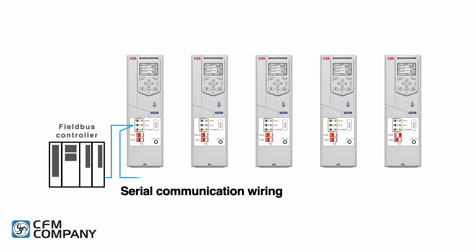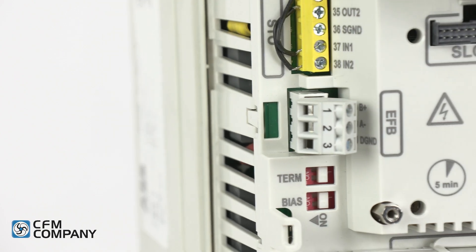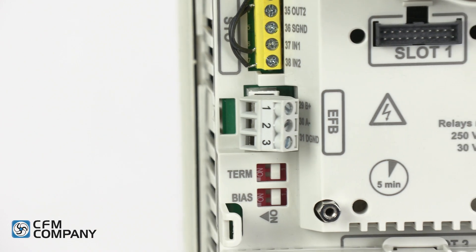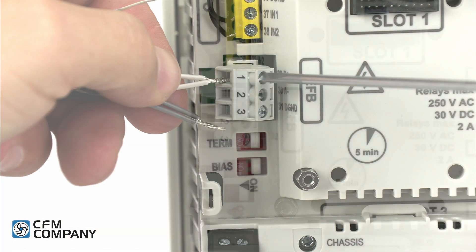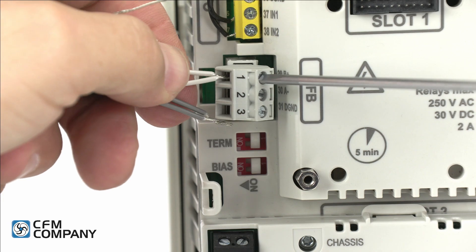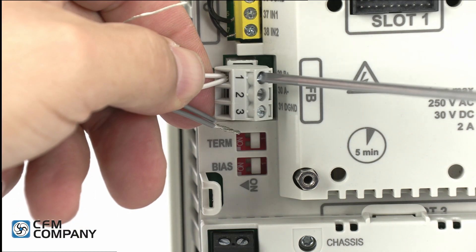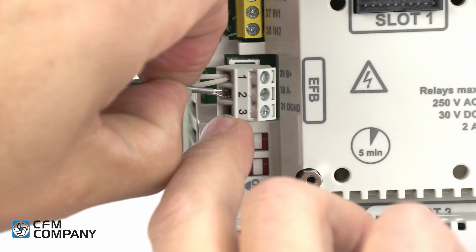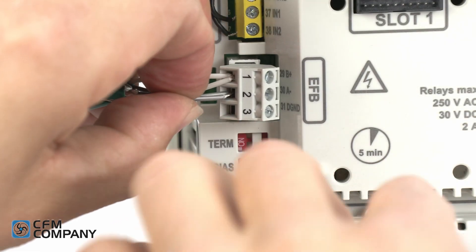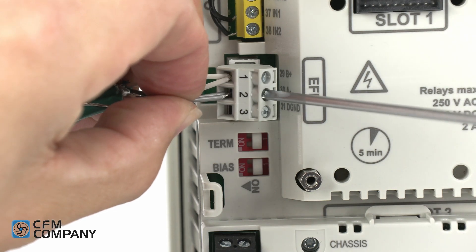If multiple devices will be connected to the network, the communication wires must be daisy chained. The serial communications wires will be landed on the removable embedded field bus terminal labeled EFB. Connect the positive network wire to terminal 29 labeled B+. In our example, this is the white wire. Connect the negative network wire to terminal 30 labeled A-. In our example, this is the black wire.